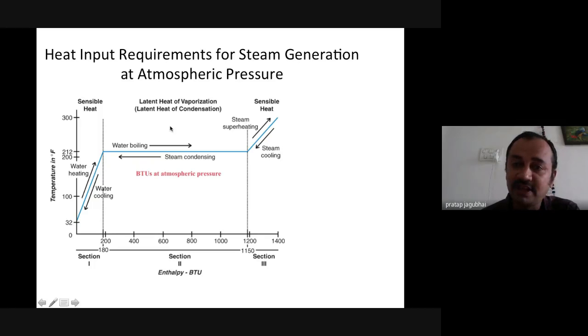So when you take away the heat, when you utilize the heat in drying or process applications, the steam becomes condensate and water. That condensate and water is taken back inside the tank, or to the hot water applications nearby your process, and the water can be utilized again. In that way the complete cycle can be completed. If the water is not contaminated with any chemical organics inside the process, it is taken back inside the feed water tank and can be reutilized.